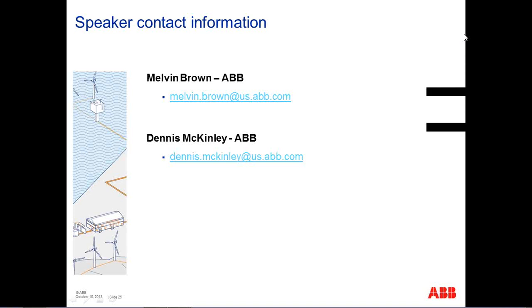All right. We've got one more question that came in. What format do you prefer for harmonic data when specifying a transformer, K rating, or the full harmonic study? Well, we prefer the full harmonic study. That's the best thing to have up front. But in a lot of cases, the developer may not have that information in place, and we wind up using the K factor. But as a preference, I would prefer the full harmonic study.